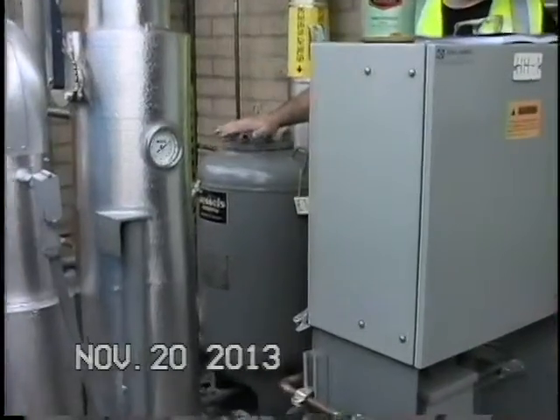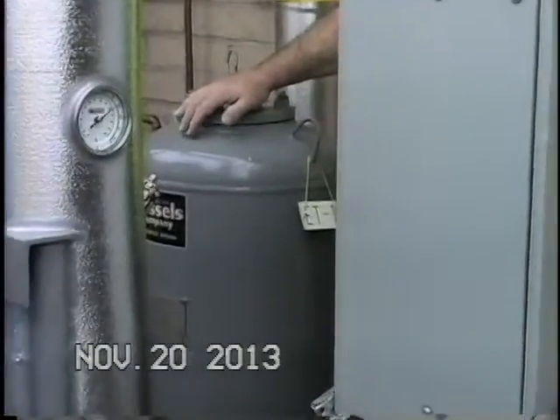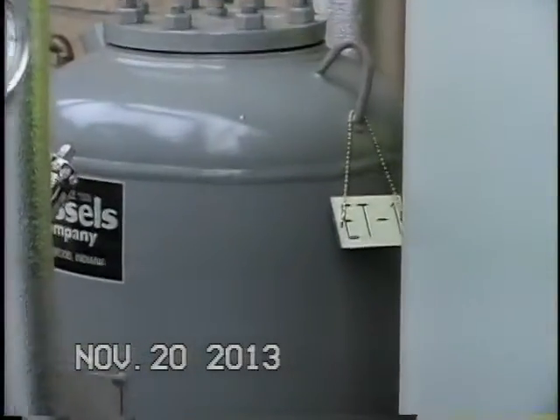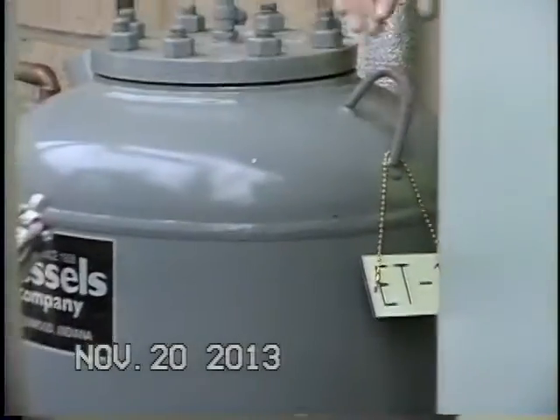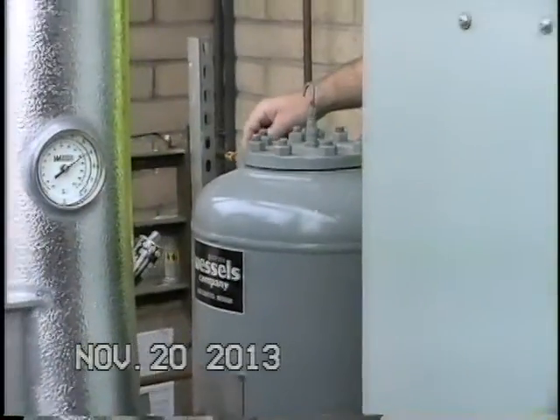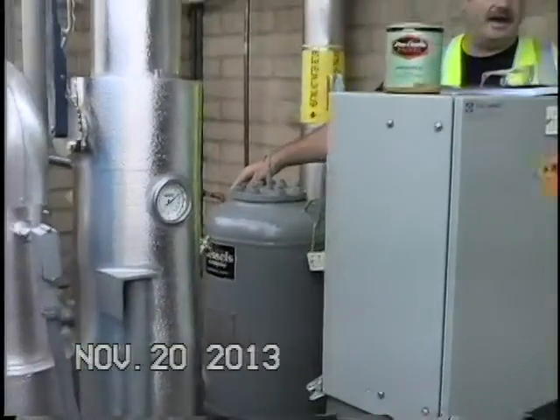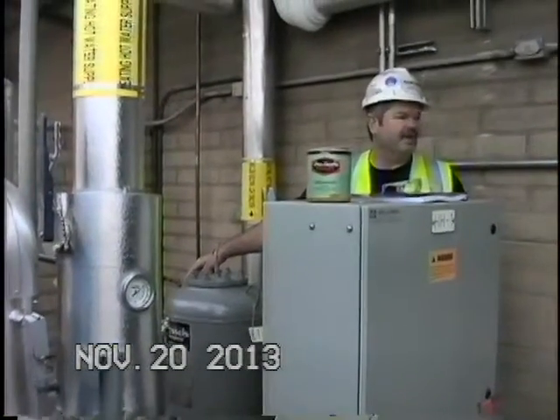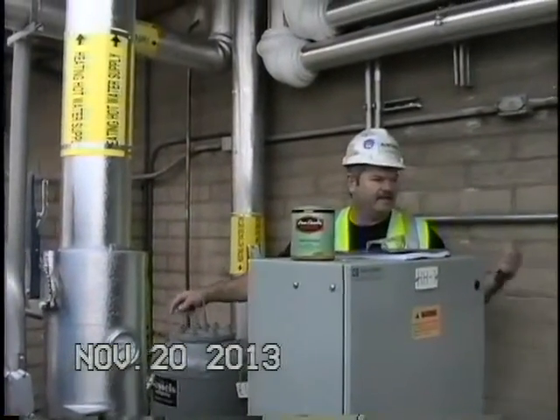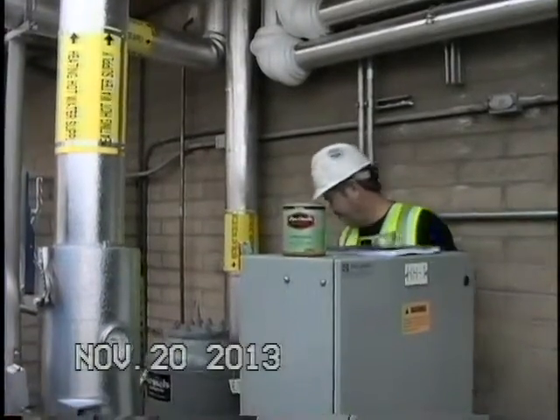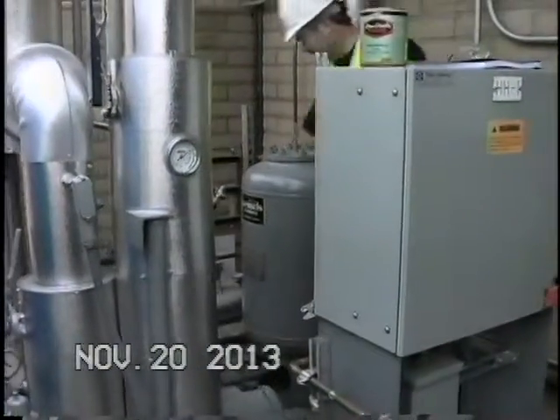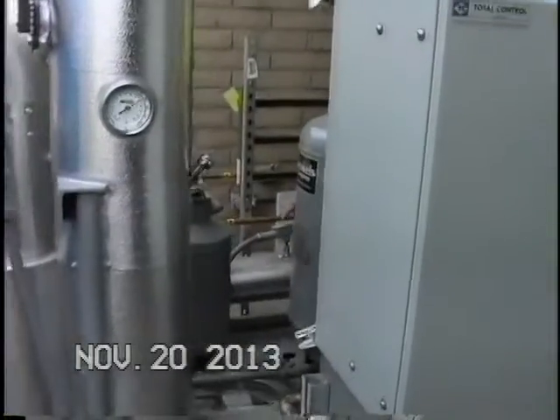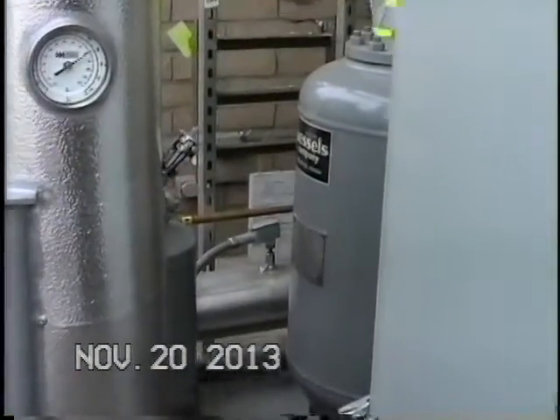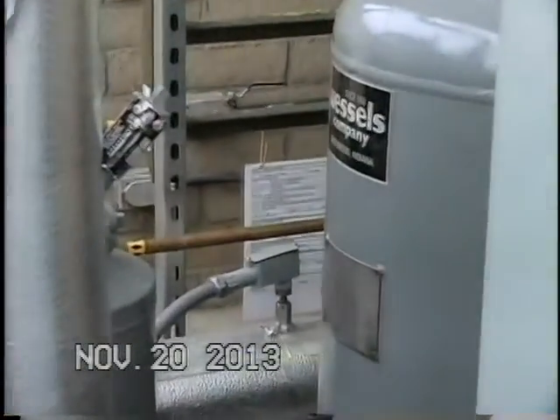And when you do that every 6 months, you've probably dealt with expansion tanks before, where you isolate it, drain it down, and then you check the air pressure. This should be about 12 to 15 psi, okay, which was set at the time when we came out here. These little things are sensors. Anytime you see these little lines, they're going to the panel or the boiler.